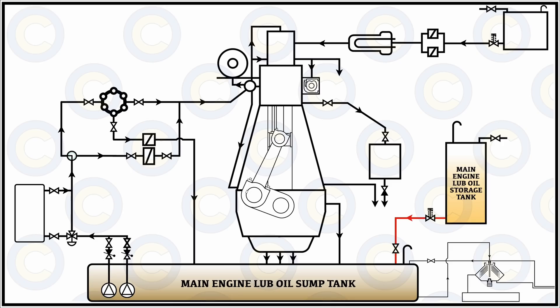From here, the main engine lube oil pumps — which are basically submersible type centrifugal pumps — will draw suction and then send this oil further. From here, this oil goes into the main engine lube oil cooler. On most ships, due to the sheer size and nature of the system, it will be sea water cooled, but on certain ships it can be fresh water cooled also.